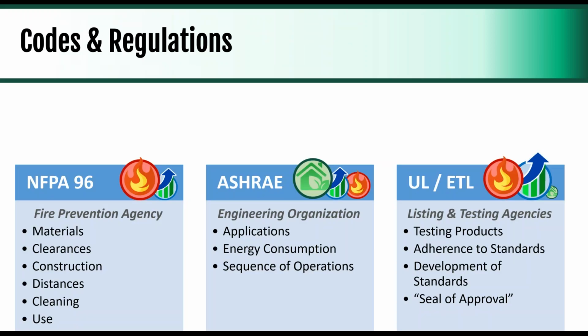Just to give you a broad overview of codes and regulations, there's really 3 buckets that we look at. The first is NFPA 96. It's very focused just on fire safety. So they're talking about what materials hoods must be made out of, clearances to combustibles, non-combustibles, what exactly those materials are classified as, different construction methodologies. Does it have to be fully welded? Does it have to be seamless? Distances, cleaning, how often it should be cleaned, i.e. ductwork, that's something that has been updated as well. And then use, so how are you using the commercial kitchen ventilation system?